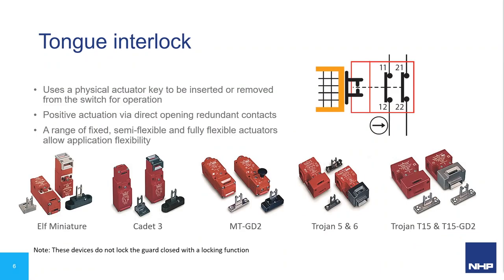Tongue interlock switches use a physical actuator key which is inserted into the switch to close the safety contacts. When the actuator is removed, the cam arrangement inside the switch forcibly opens the contacts to remove power from the safety control circuit, ensuring that even if contacts are stuck closed due to corrosion or welding, the force of physically removing the actuator breaks them open. The actuator is a special shape so only the correct actuator can enter the switch — you can't use a screwdriver or metal shim. The Guardmaster miniature ELF and Cadet 3 are ideal for small machines such as printers, copiers, and domestic machinery where space is limited.